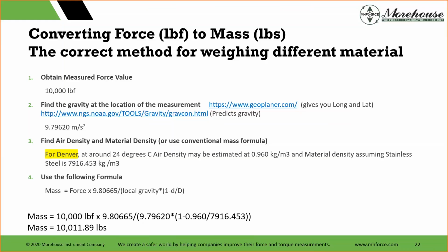It means really that in Denver, you read it two ways. In Denver, to generate 10,000 pounds of force, they would need their mass adjusted to 10,011.89 pounds. If we did the calibration here and sent it to Denver, that would equate to that. So you can read it both ways.